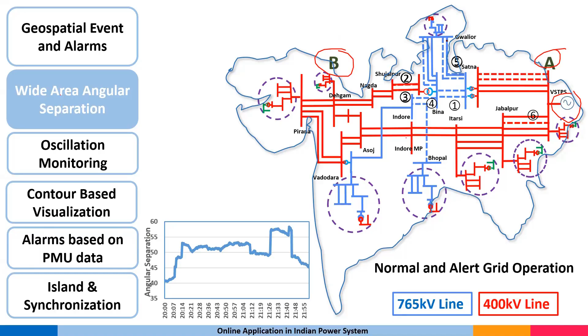Then there are events of oscillation, electromechanical oscillation, due to the non-linear nature of the power system. This is because the power system is basically a combination of different machines running at a synchronized frequency. However, there is an electromechanical part because all these machines have a mechanical part also connected, which is producing the electrical power. So if this mechanical power oscillates, it results in this kind of oscillation in the system.